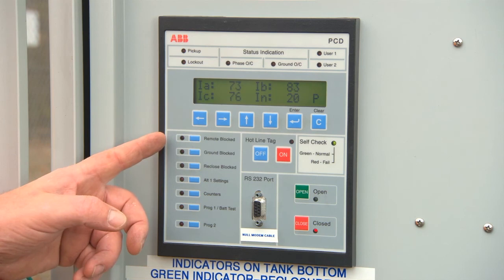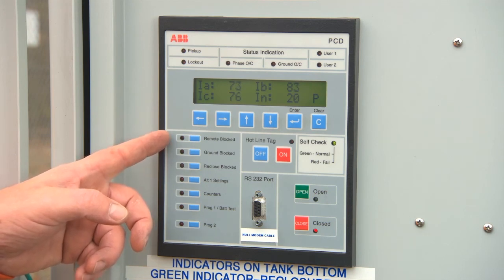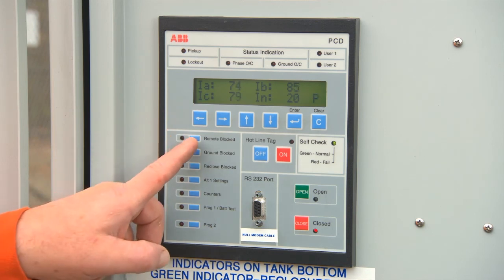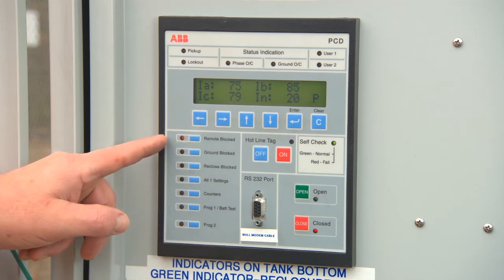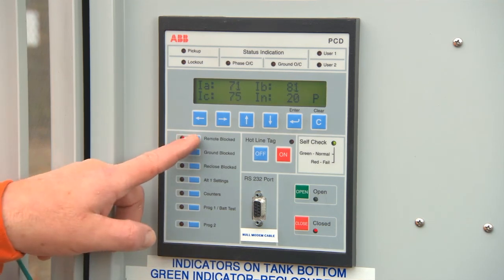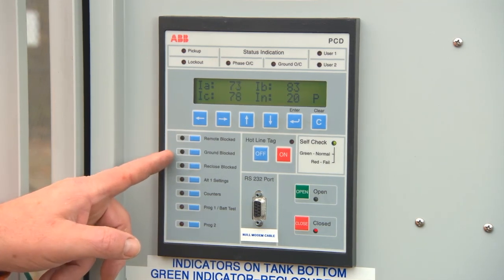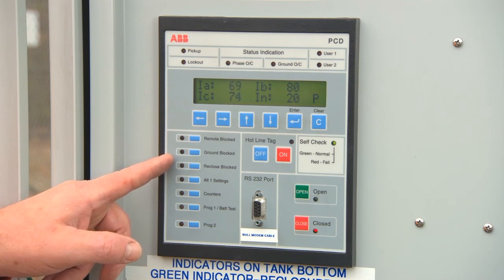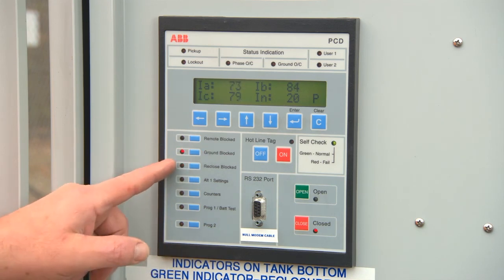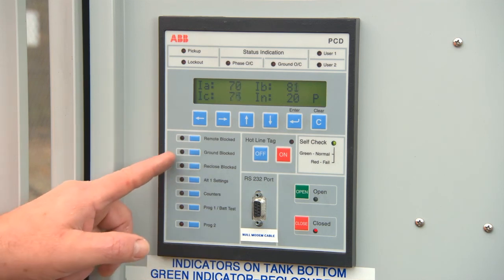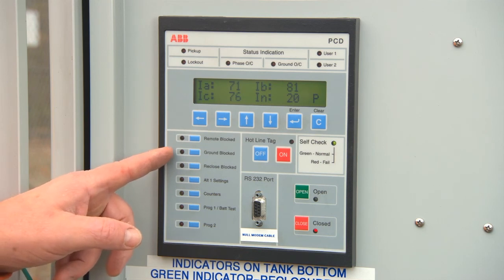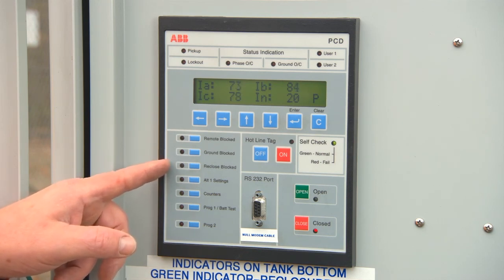Moving down along the left side of the unit, we have Remote Blocked. This is only active when communications are linked to the unit. To block communications, press this button and the indicator will turn red. Press it again and the indicator will turn off. Next is the ground block. This will turn red after applying the block to the ground. Pressing this button will block your ground settings. Press again to turn this feature off. Ground block is typically used for switching in and out of service or switching through one of these reclosers.